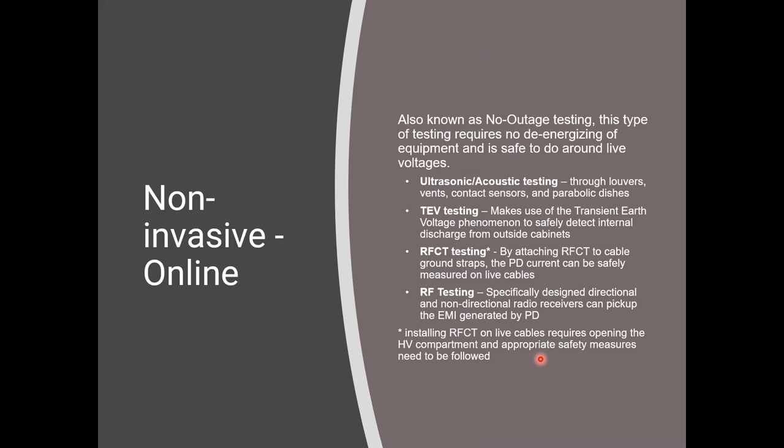The non-invasive tests are also known as non-outage online tests. They're typically portable, handheld instruments that use different technologies to identify PD without having to take the equipment offline. So it uses your utility source voltages. You don't typically have an external voltage source to run the test. So it's running on your nominal voltage, and you typically don't have to de-energize things to do your test.